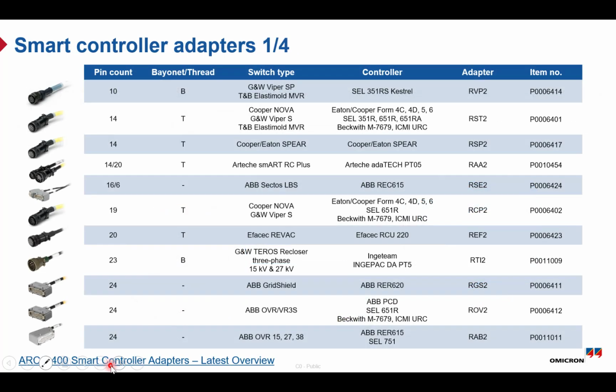Now let's talk about smart controller adapters. To connect the ARC 400 to different Recloser controllers, we use dedicated adapters. These adapters act as the interface between the test set and the controller, allowing quick and correct connections without manual wiring. Each adapter is designed for a specific control type or controller, for example, different pin configuration like 24-pin connections. The adapters themselves are short cables and they are typically used together with extension cables up to 7 meters. The extension cables allow you to work comfortably in the field.